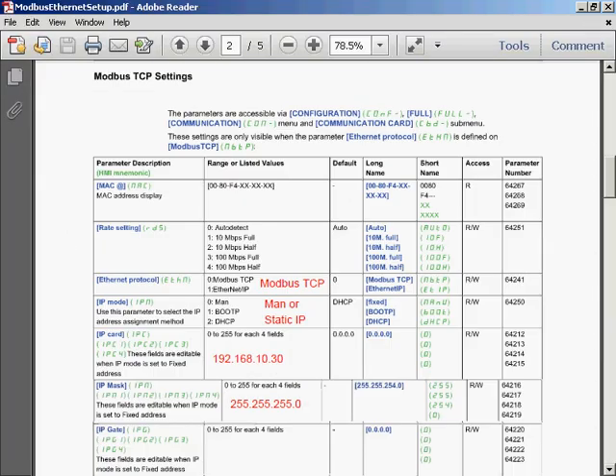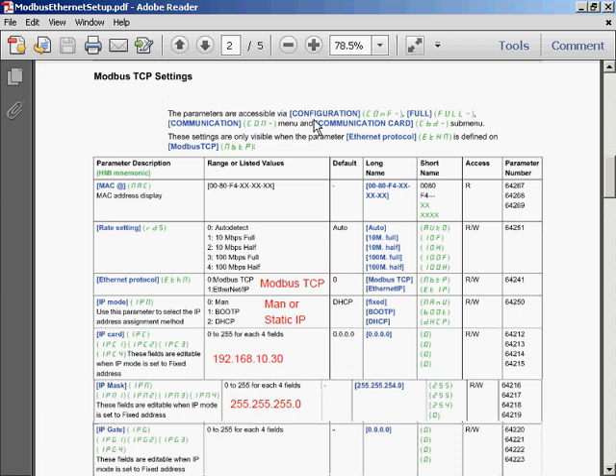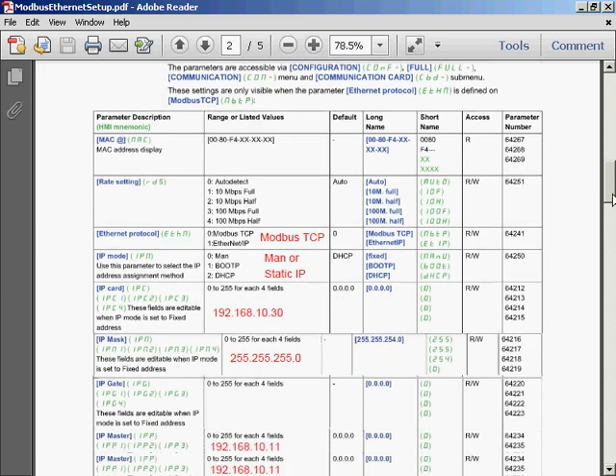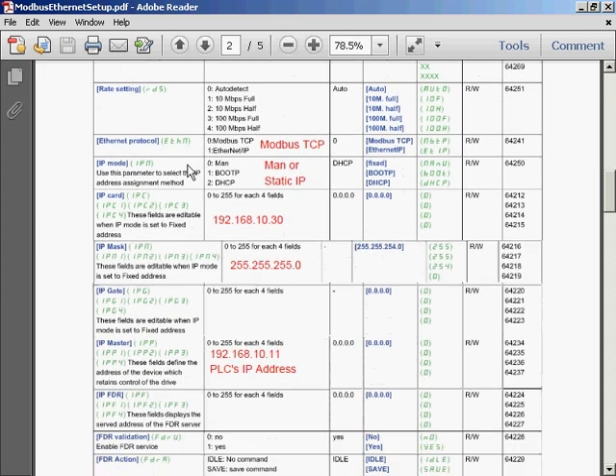So let's look at the Modbus TCP settings of the drive. If you go under from the display of the drive itself, under the Configuration menu, Full Comms, Communication card, you'll notice the following settings. We are going to make sure the Ethernet protocol is set to Modbus TCP. We have our choice. We're going to set a static IP address in there of 192.168.10.30. I'm going to give it the subnet mask.